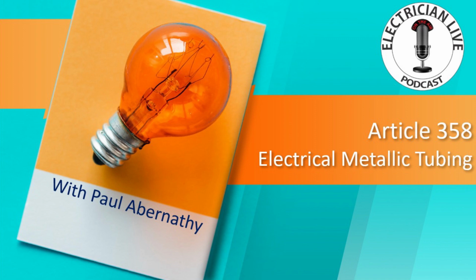Okay, and I don't have to size that equipment grounding conductor. I don't have to utilize 250.122. Now, again, I'm a wire and cable guy. I'm not going to sit over here and cheer the kudos for the conduit folks or the tubing folks, okay? I love them because they protect my wire, but at the end of the day, this is just giving you an allowance to use the EMT as an equipment grounding conductor, not a requirement to use the EMT as an equipment grounding conductor, okay? Just want to make it clear.